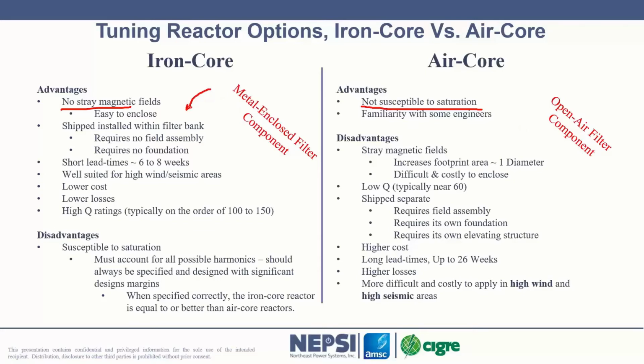And it is why I say that you want to make sure that your filter current specifications are high. You want to specify the harmonic current that the reactor is going to be asked to filter or to conduct as much higher than what maybe you had estimated in your analysis. So a conservative reactor specification, especially when it's iron core, is highly advisable.